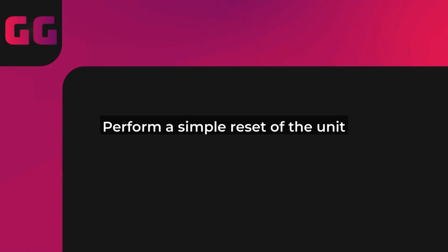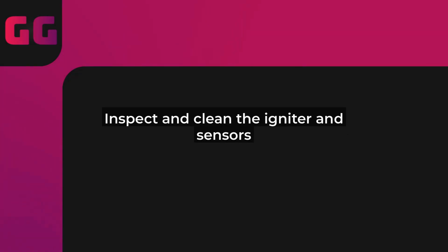These components can get dirty over time, so grab a soft brush or cloth and gently clean any buildup. Make sure the igniter is properly aligned and not damaged. Look for cracks or wear. While you're at it, check the venting system for blockages, as poor ventilation can cause flame issues. Rinnai heaters need good airflow, so clear out any debris from the exhaust and intake vents.